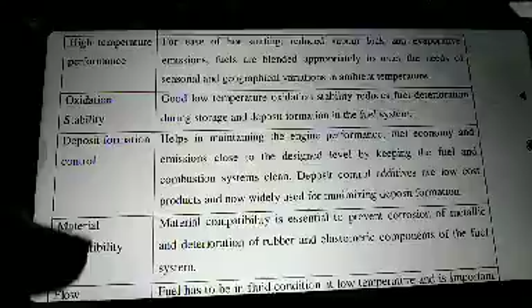Material compatibility. The material compatibility is also essential to prevent the corrosion of metallic and deterioration of rubber and elastomeric components of the fuel system. Flow characteristics are also important. Fuel has to be in the fluid condition at low temperature, and this is important particularly for diesel fuels. Also, appropriate diesel fuel viscosity is essential for flow as well as good injection characteristics.